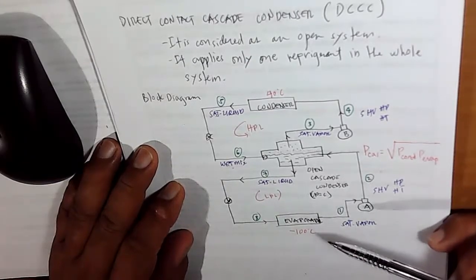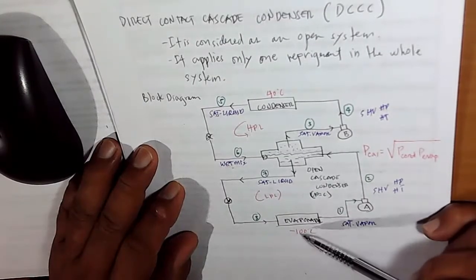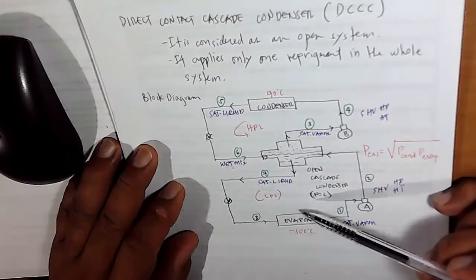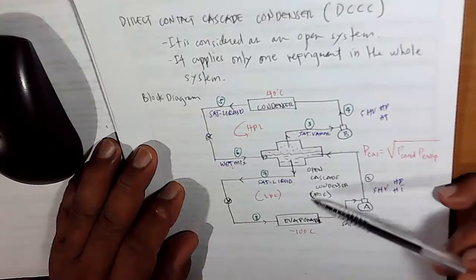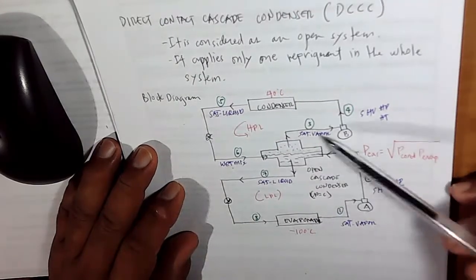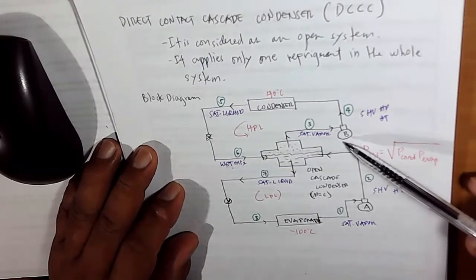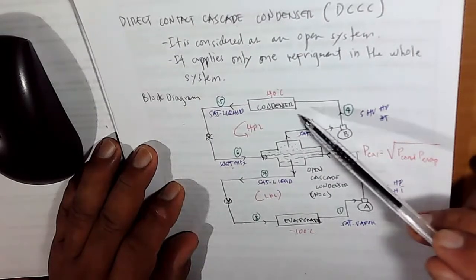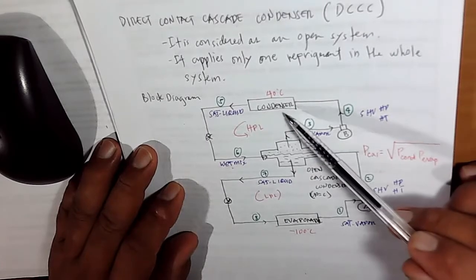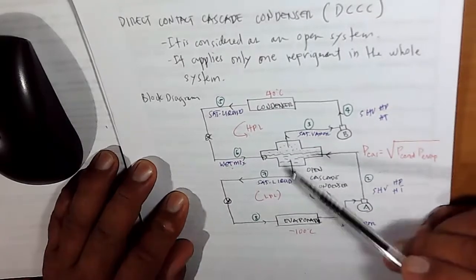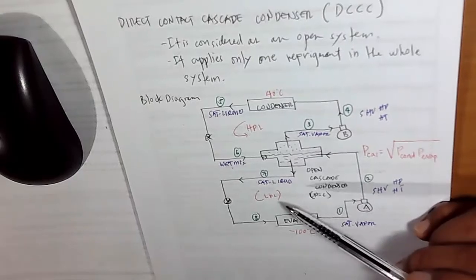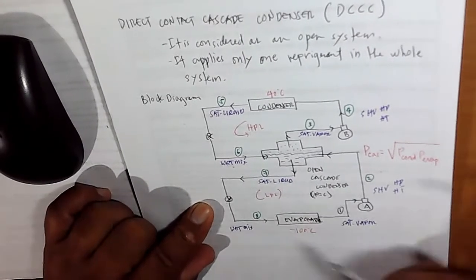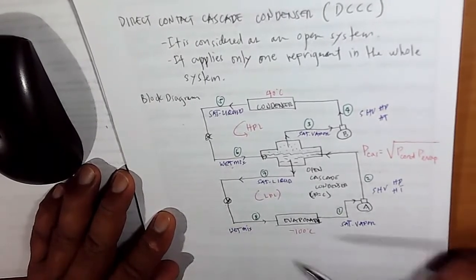There is an exchange of heat from the very low temperature of negative 100 degrees Celsius going up to 40 degrees. The heat coming from the very low temperature will be stored in your cascade condenser before going to the compressor, which will later convert both mass and heat from the cascade condenser into superheated vapor at high pressure and temperature, before it goes to your condenser. At point 7, it is once again converted to saturated liquid, passing through your expansion device at constant entropy, thereby changing once again into a wet mixture before going to your evaporator, and then your cycle continues.